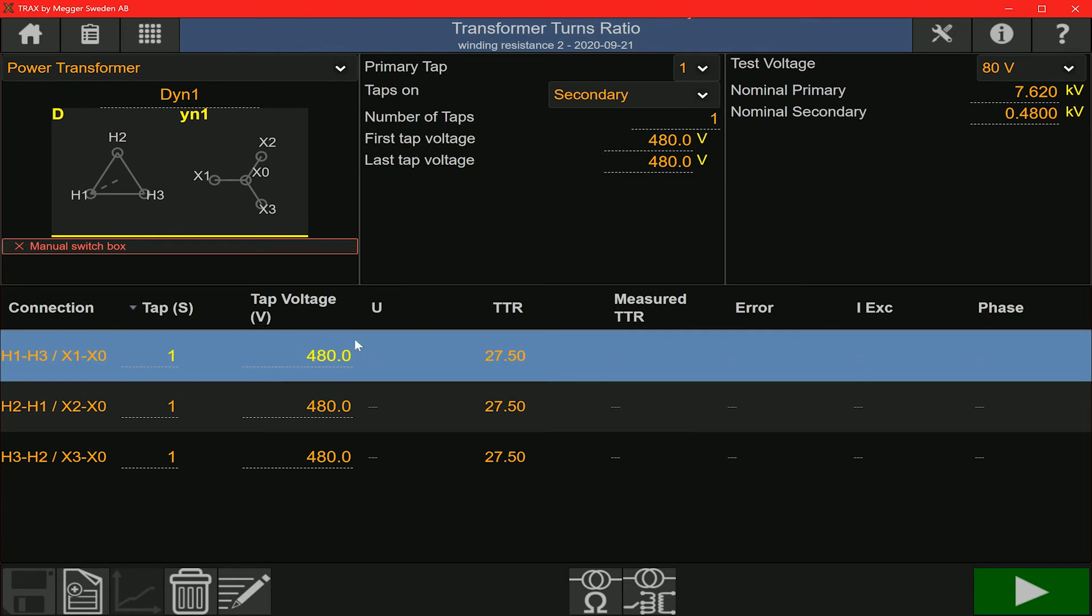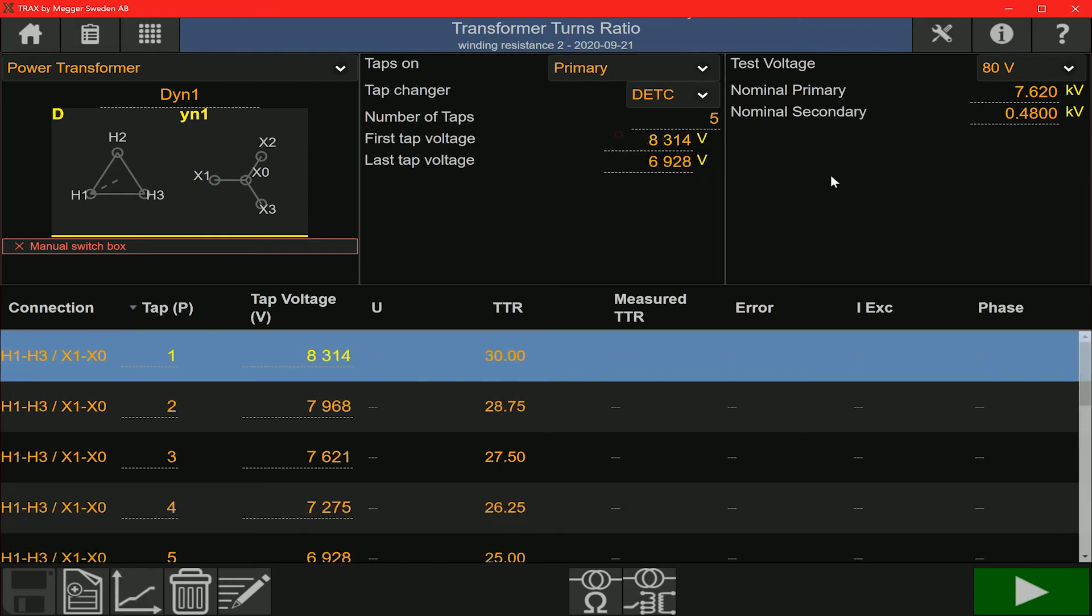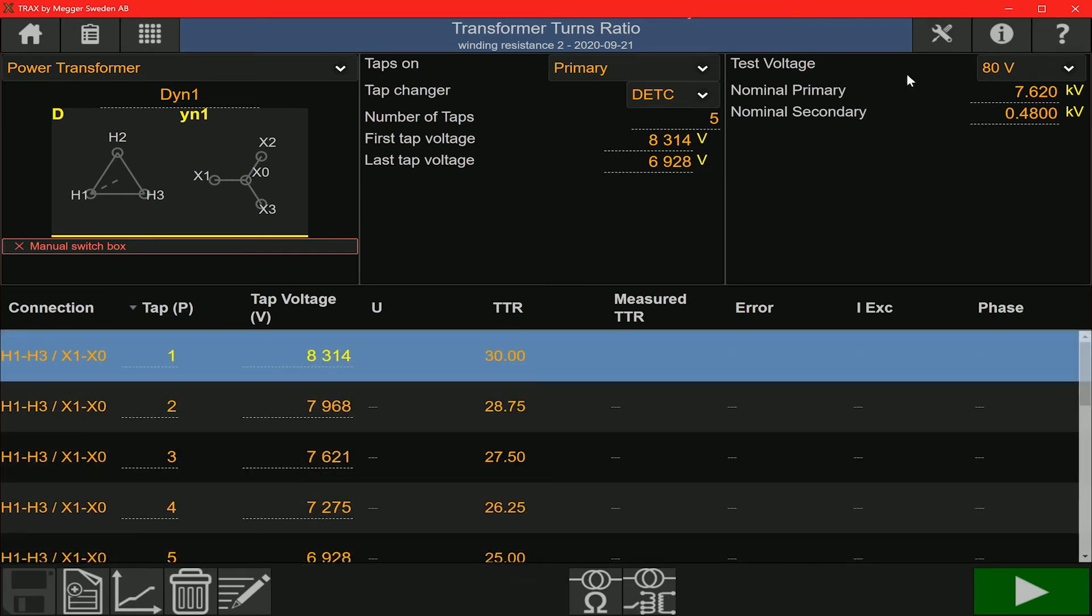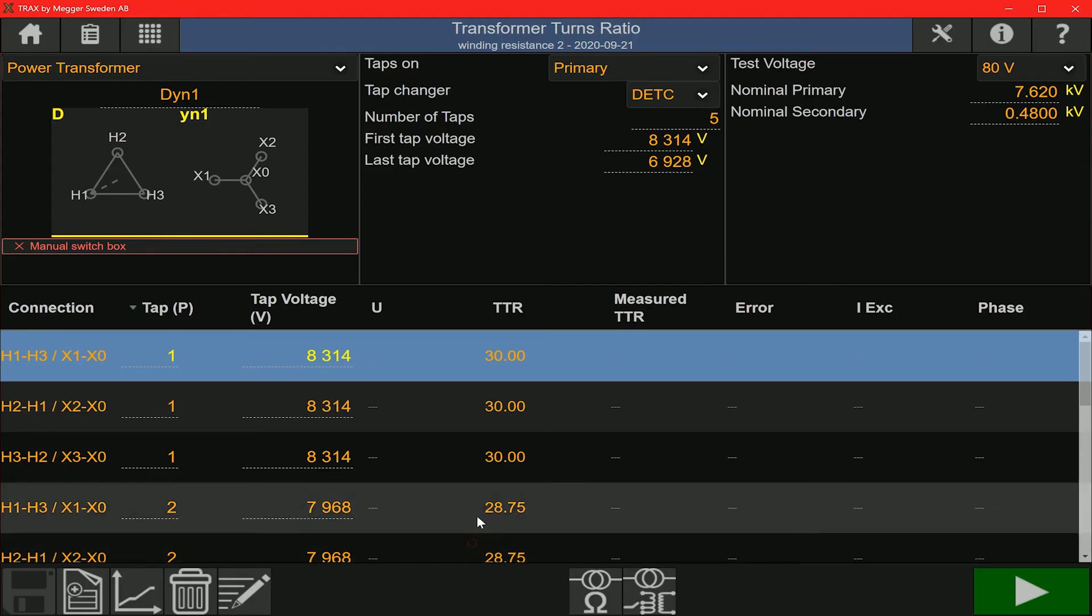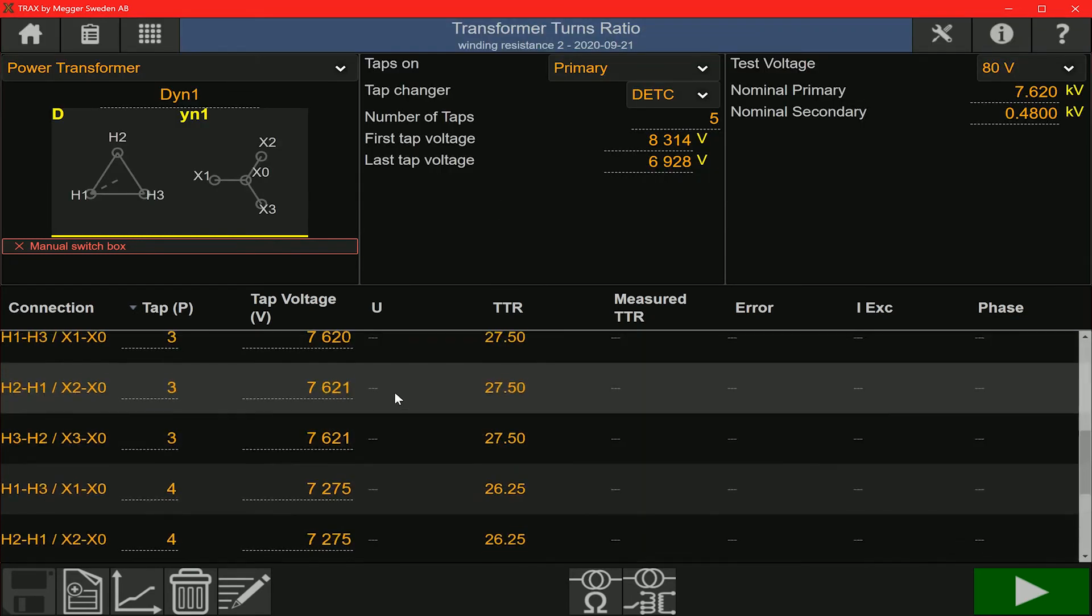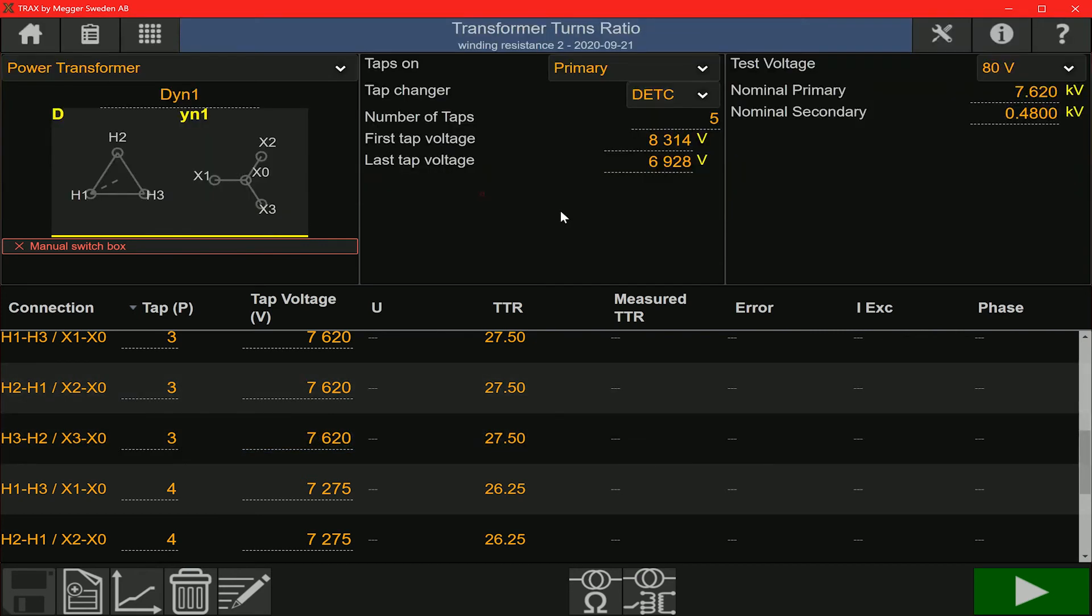This is the secondary turns ratio screen and you can switch between the primary and secondary. You can run the test on either screen. It doesn't matter as long as the tap position is selected correctly. The connection order setting has two options: either by tap or by winding. I switched to by tap here and you can see that the test rows are arranged in the order of the tap position. So it's tap 1 ABC, tap 2 ABC, so on and so forth. If the tap voltage values that populate in the test section don't match with the nameplate values, you can manually edit those values. Typically that won't happen, but if there's a little bit of a difference, you can always edit the values.